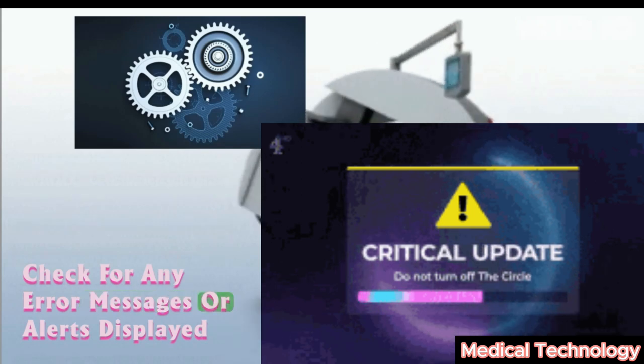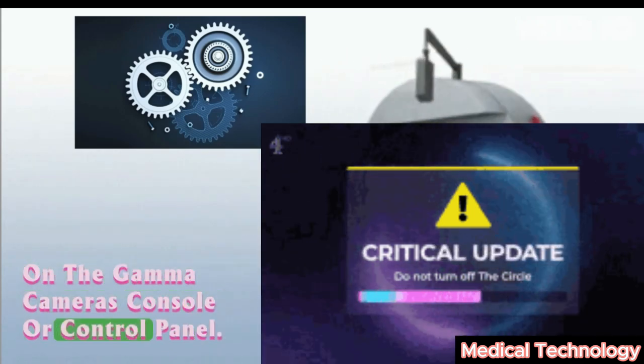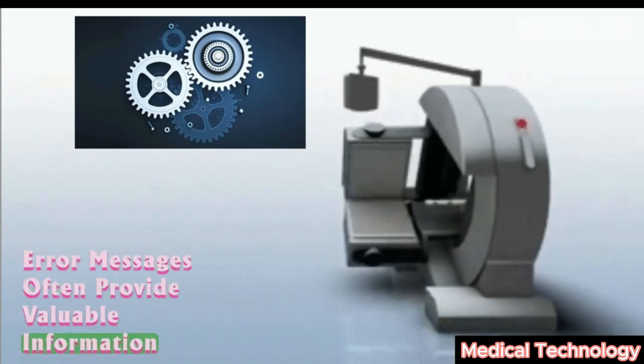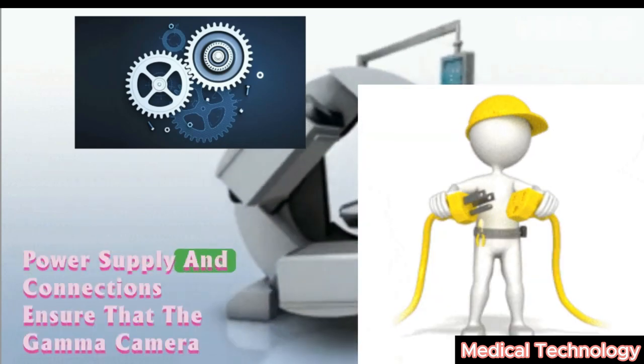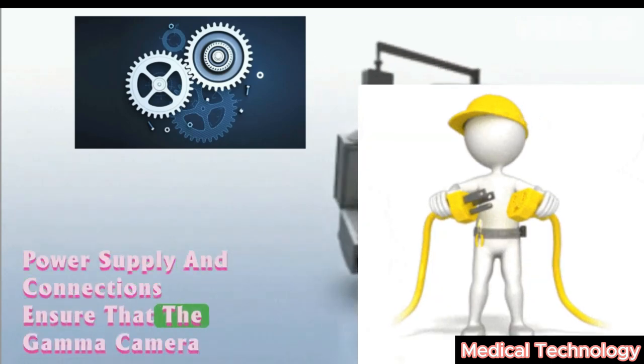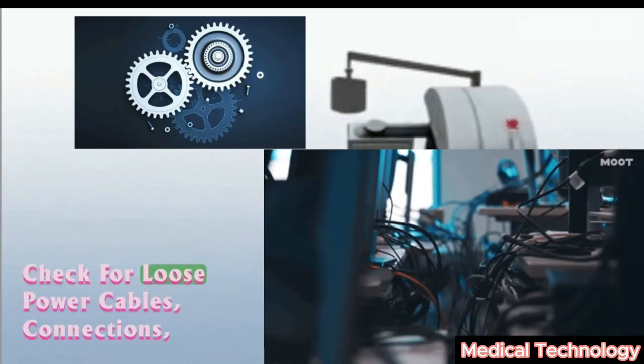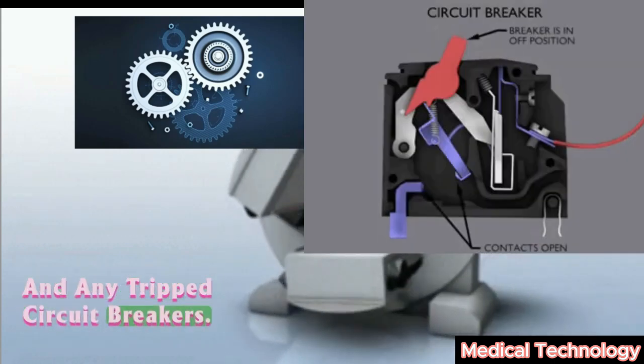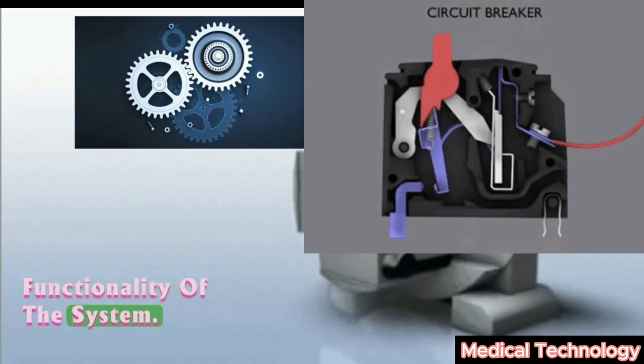Error messages and alerts: Check for any error messages or alerts displayed on the gamma camera's console or control panel. Error messages often provide valuable information about the nature of the problem. Power supply and connections: Ensure that the gamma camera is properly connected to a stable power supply. Check for loose power cables, connections, and any tripped circuit breakers. Power issues can affect the functionality of the system.